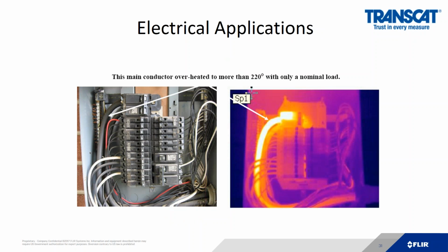In this example, the main conductor overheated to more than 220 degrees with only a nominal load. One of the things we know right out of the gate is that when there's an infrared problem or a hot spot on your target, it's always best to know the load, because the load would indicate how hot that target is at the moment or could have been. A faulty conclusion would be that target is measuring at 220 degrees and that's the hottest it's ever been. Because if it was lightly loaded at that time, and someone applied more load to the application, that temperature would skyrocket exponentially.